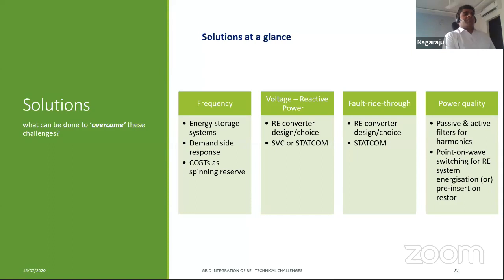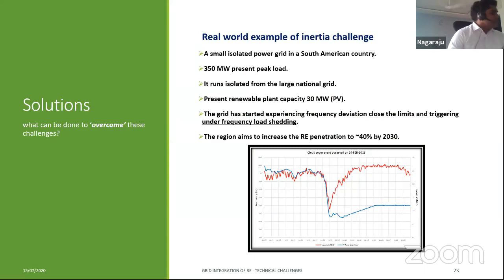But it doesn't work all the time because it requires a lot of sophisticated measurement systems and very quick acting circuit breakers. Other solutions we do provide is pre-insertion resistors. When they energize the wind farms, during the energization, these resistors come into the system in series and absorb the energy instead of impacting the grid. I'm not going into that detail because it's a bit too technical to explain. So I just limit myself to the harmonics side. Okay.